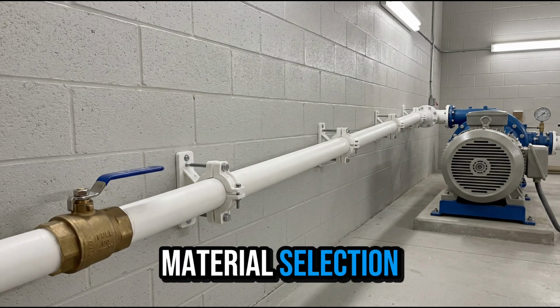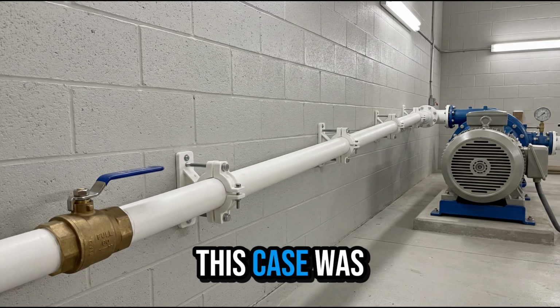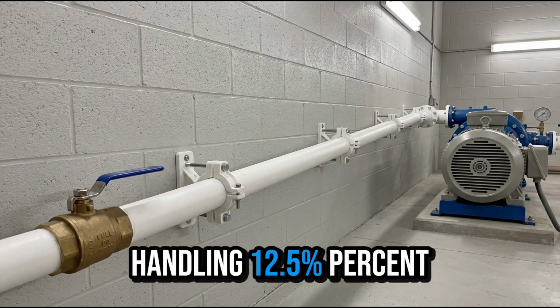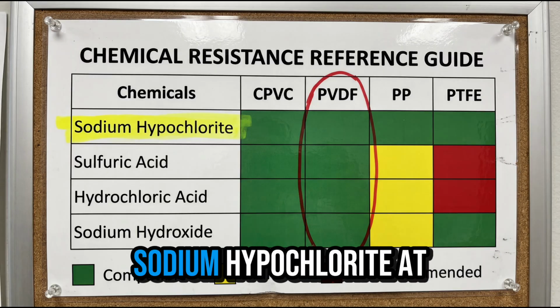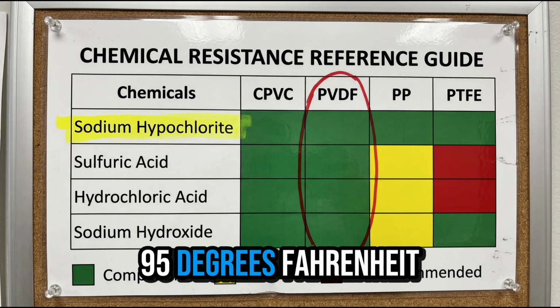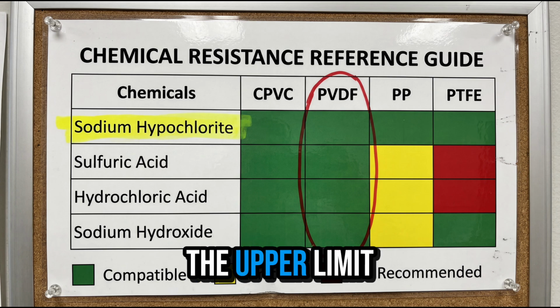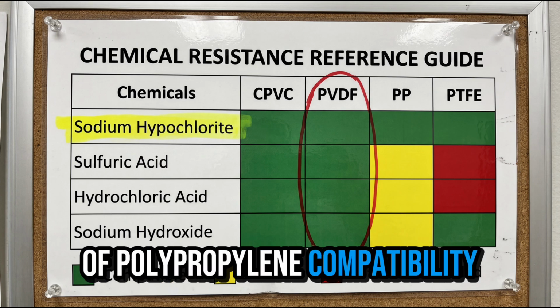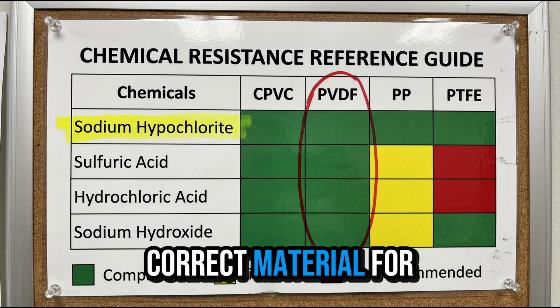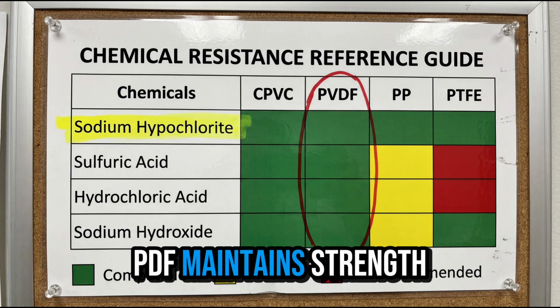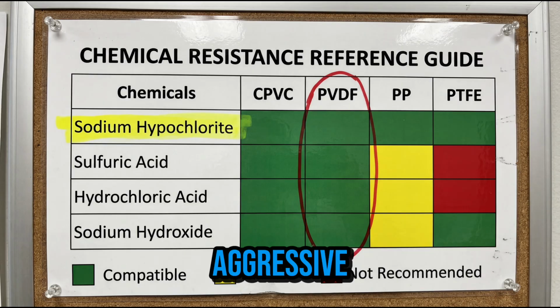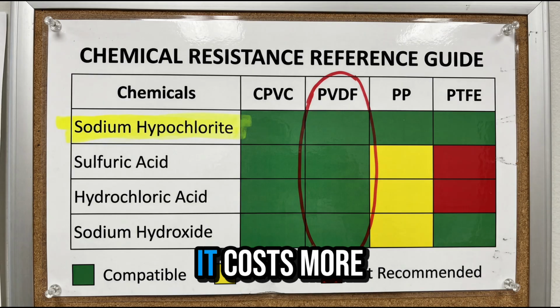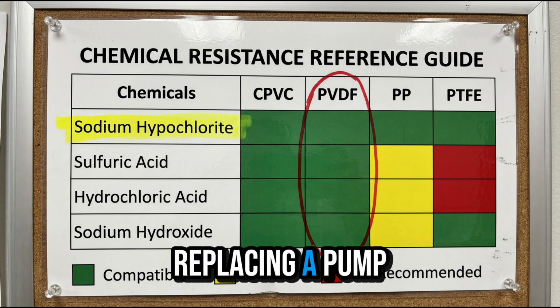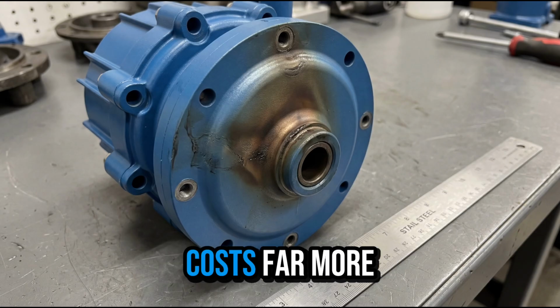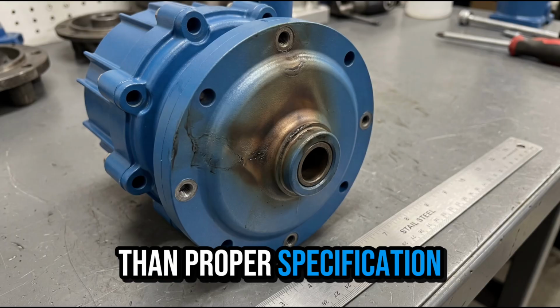Now, material selection. The pump, in this case, was polypropylene handling 12.5% sodium hypochlorite at 95 degrees Fahrenheit. That is near the upper limit of polypropylene compatibility. PVDF is the correct material for that duty. PVDF maintains strength and stability in aggressive chemical environments. While it costs more upfront, replacing a pump multiple times per year costs far more than proper specification.